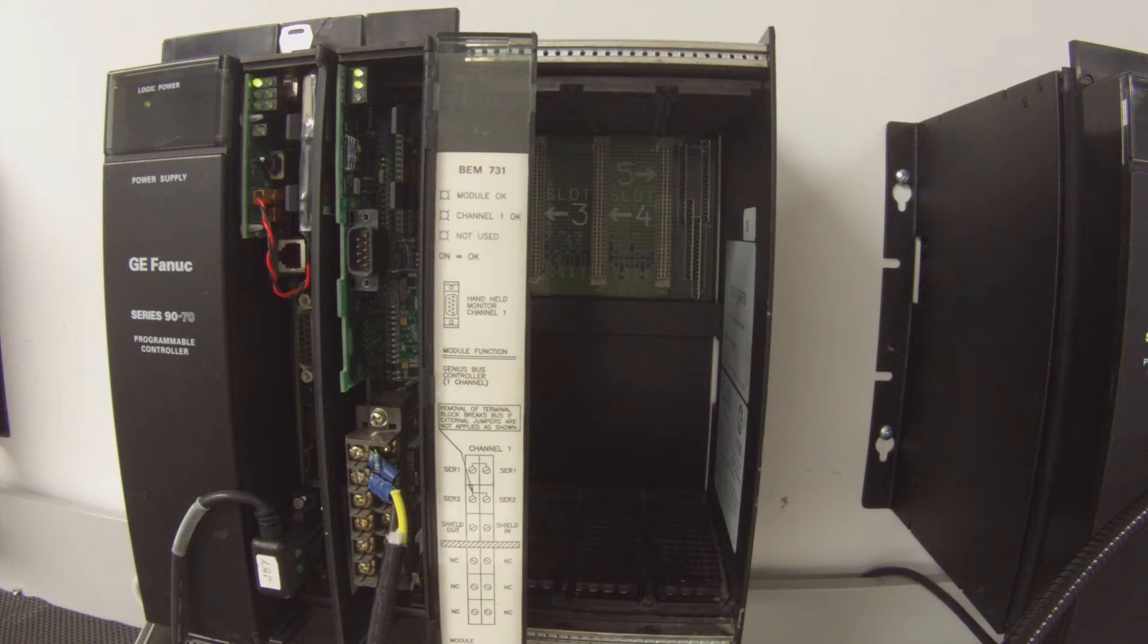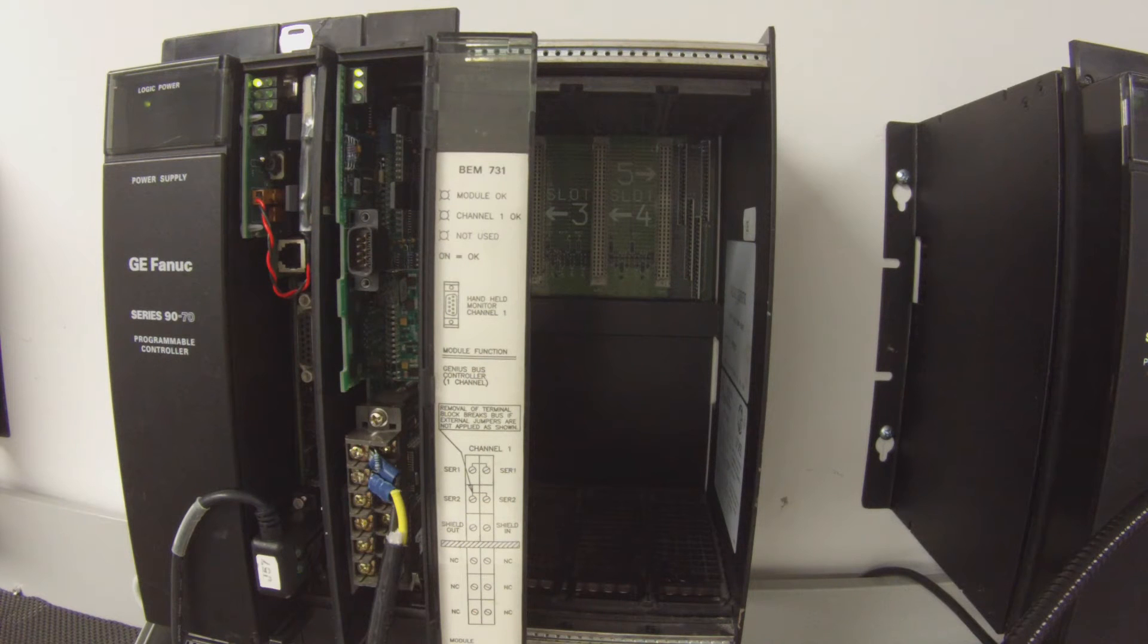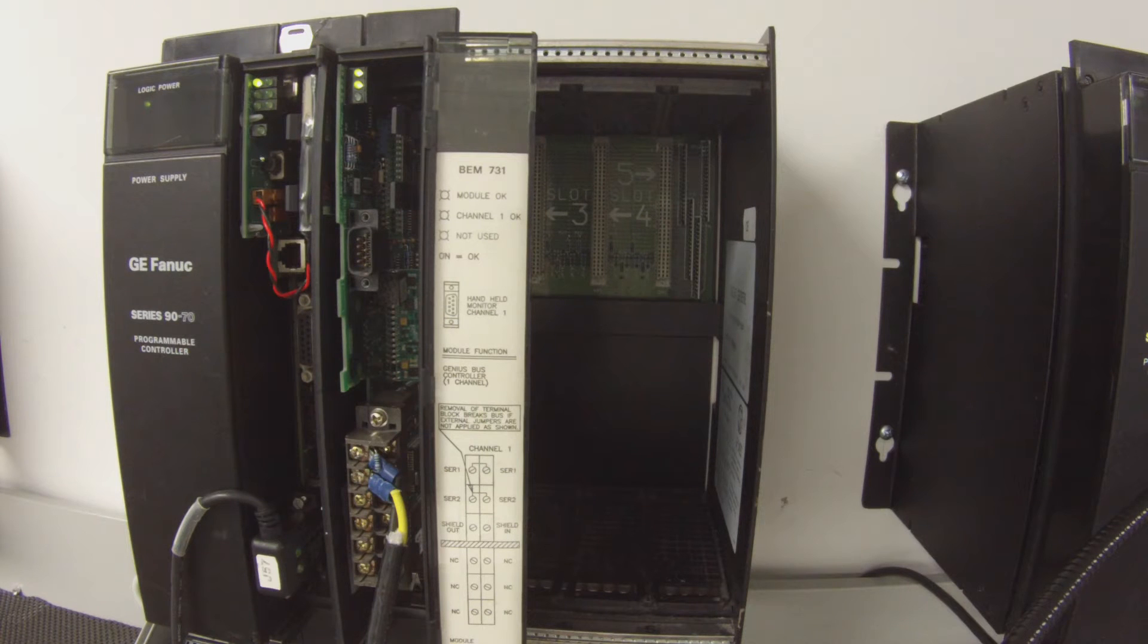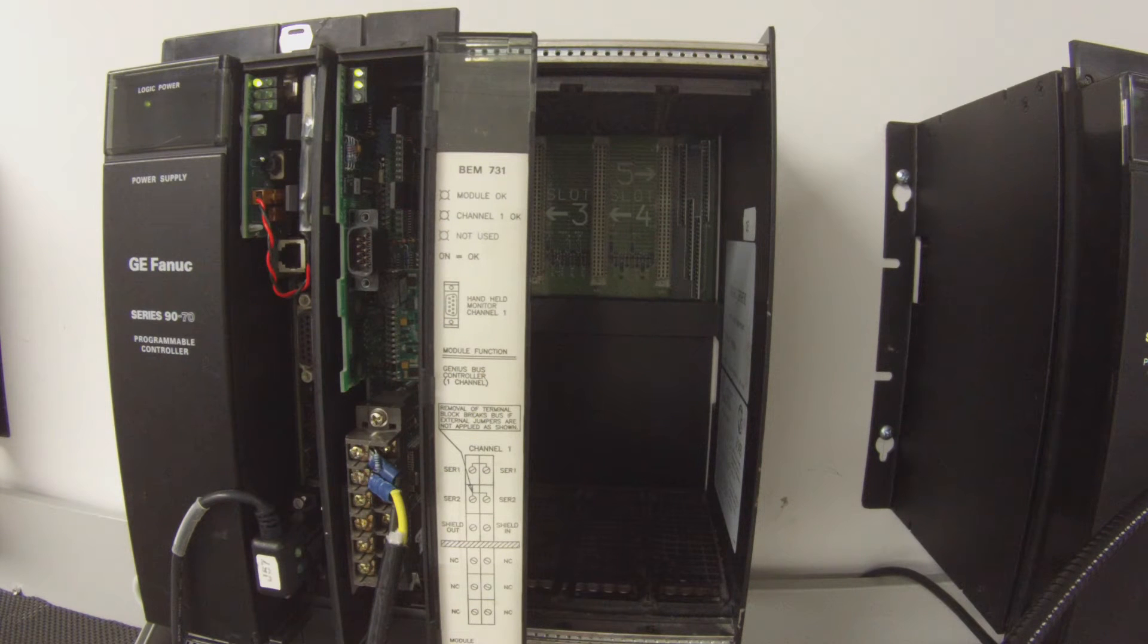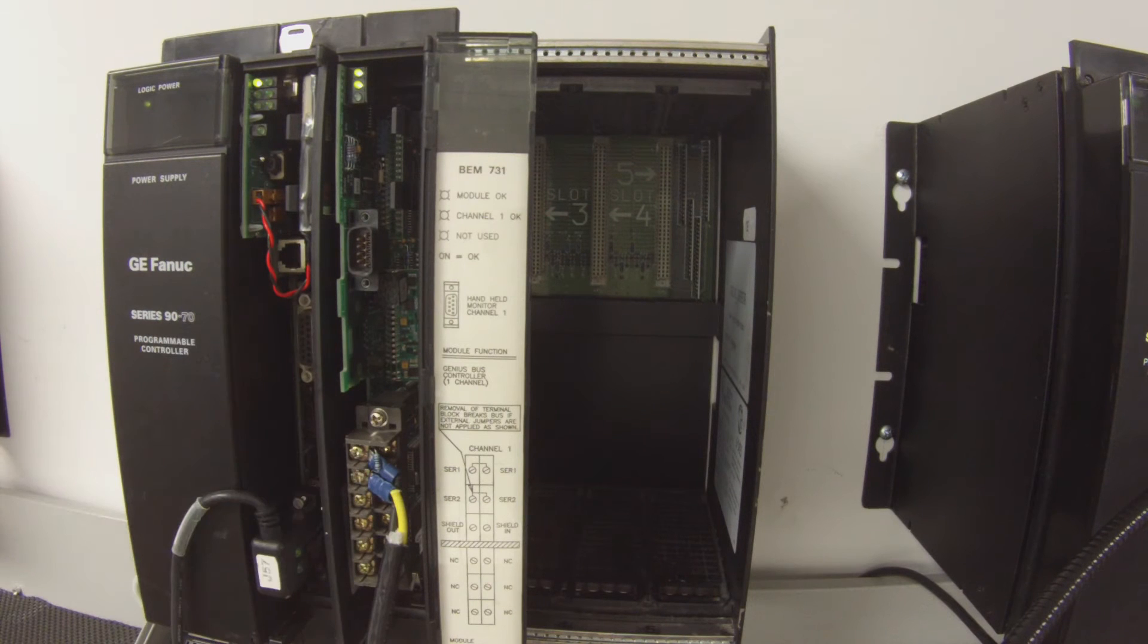So then once that's selected, I'm going to go to Target, Online Commands. I'm going to hit Clear. And I'm going to clear Controller Fault Table and I.O. Fault Table. Those are the only two that you want to do because we're just asking the processor to do something different than it was doing before. So hit OK.